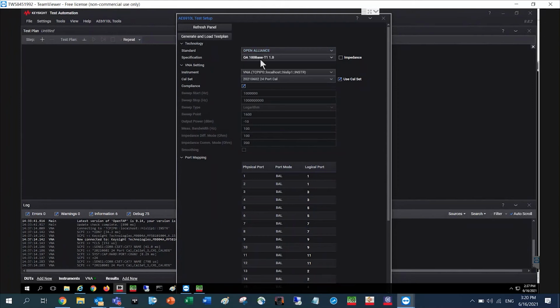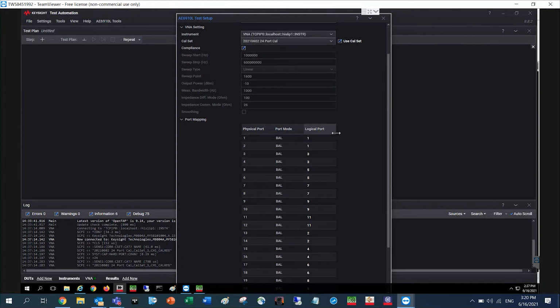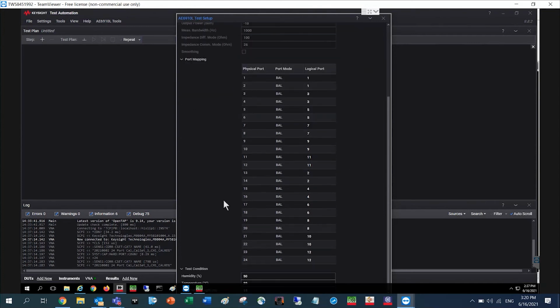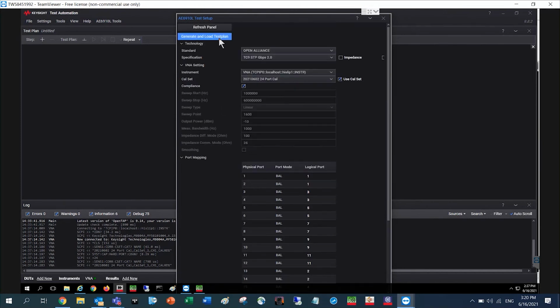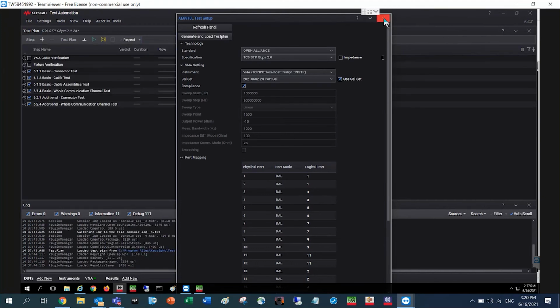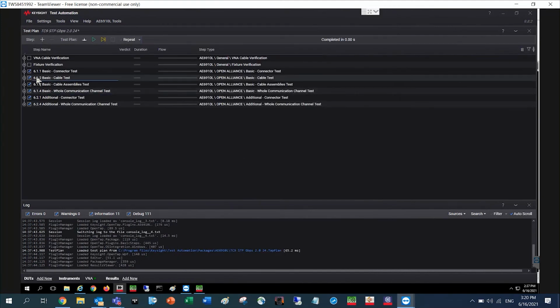Here we can set up what instrument we're using. We're using the PXI chassis, and this is the calibration file we saved previously. At the very bottom here, you can see the port mapping of the ports. And once everything is selected, you can go and generate and load the test plan. Once this is done, a test plan of the TC9 spec is generated.